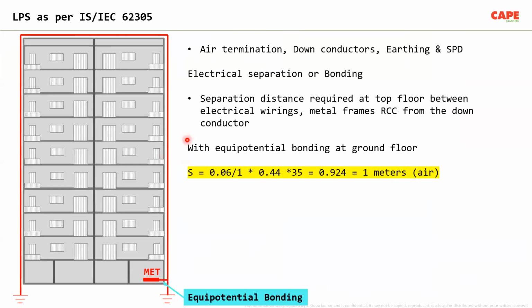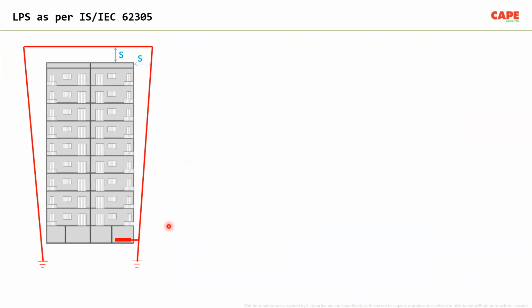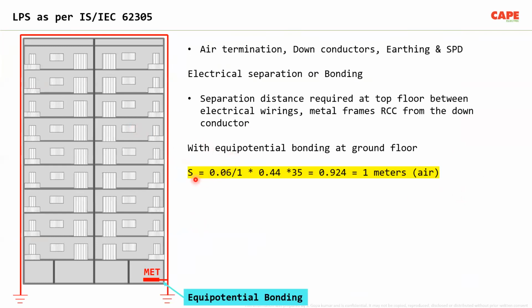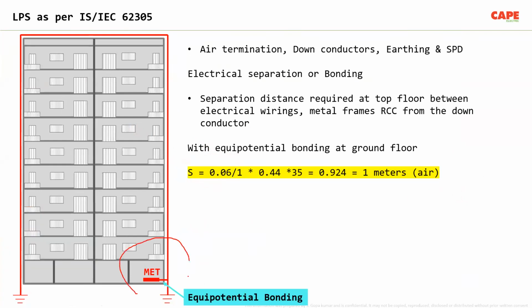Now the subject here is, you see, there is a subject in lightning protection which is called a separation distance. What does this mean? At the location where I am highlighting at the bottom, you have an equipotential bonding. Whenever there is a current flow through the down conductor, due to the surge impedance of the conductor, a high potential is created where I am marking in red. A high potential difference between the down conductor and the metal parts in the building is created.